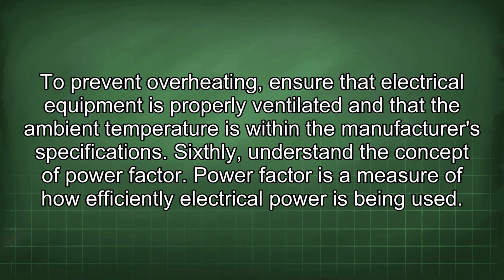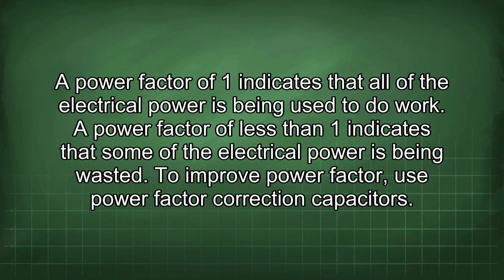To prevent overheating, ensure that electrical equipment is properly ventilated and that the ambient temperature is within the manufacturer's specifications. Sixthly, understand the concept of power factor. Power factor is a measure of how efficiently electrical power is being used. A power factor of 1 indicates that all of the electrical power is being used to do work. A power factor of less than 1 indicates that some of the electrical power is being wasted. To improve power factor, use power factor correction capacitors.